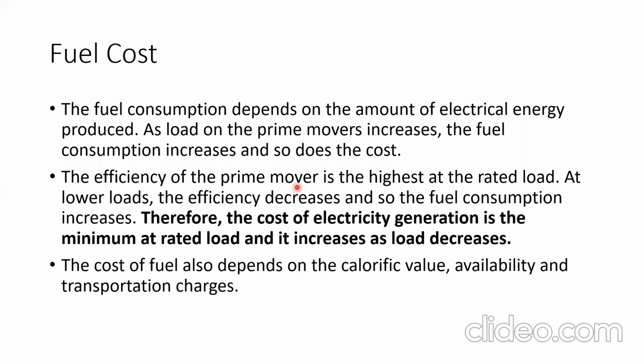The efficiency of prime mover is highest at the rated load. At lower load the efficiency decreases, so the fuel consumption increases. Therefore the cost of electricity generation is minimum at rated load and increases as load decreases. This law governs all electromagnetic machines - they work at higher efficiency when running at rated load, and efficiency decreases as the load goes below the rated load.